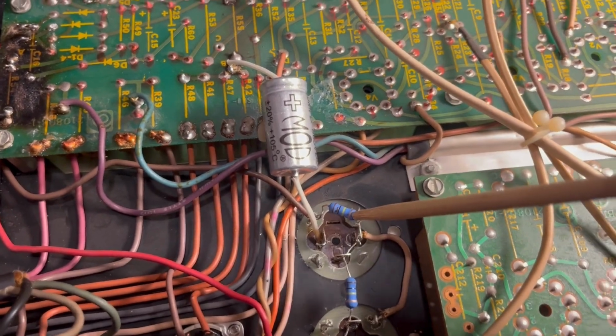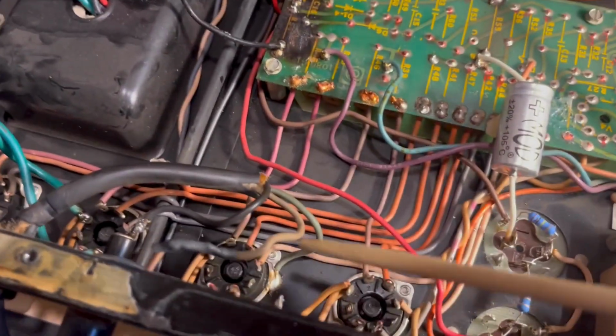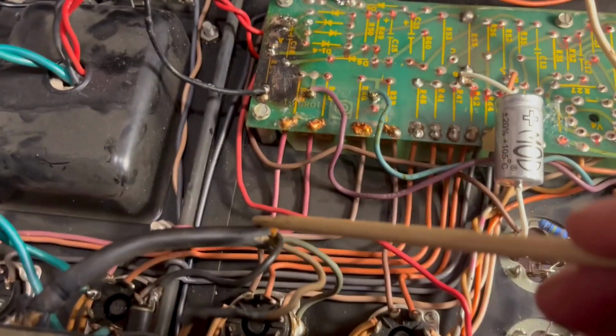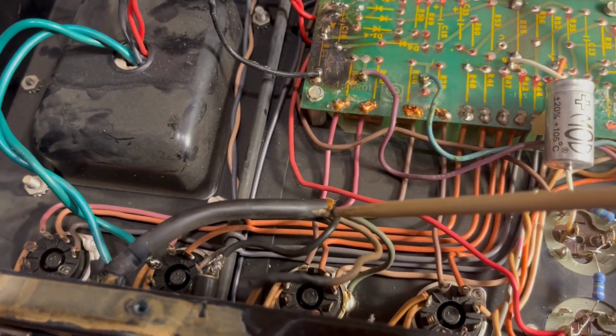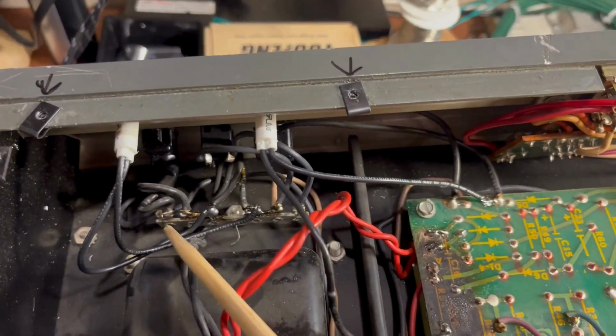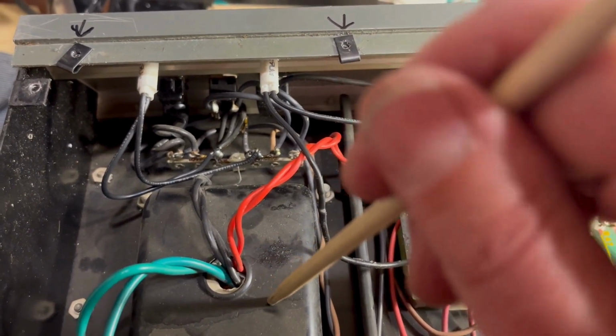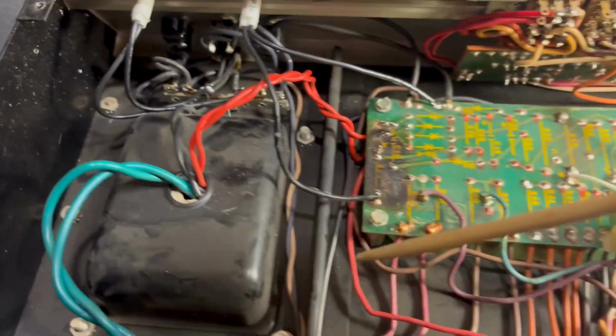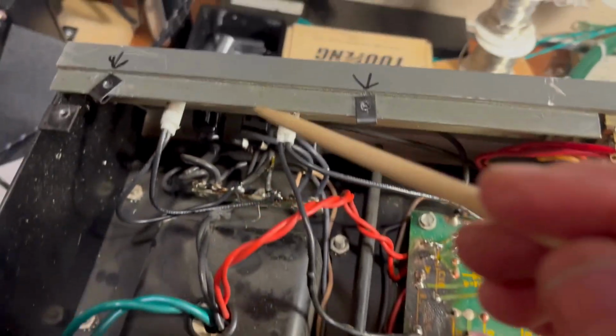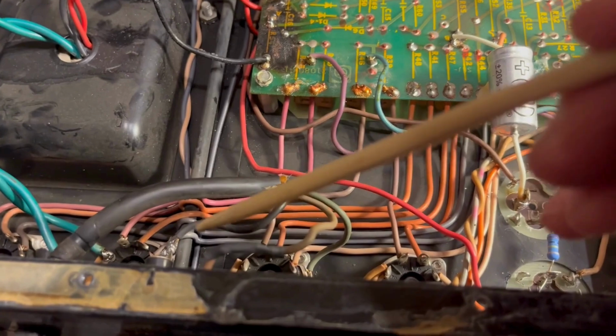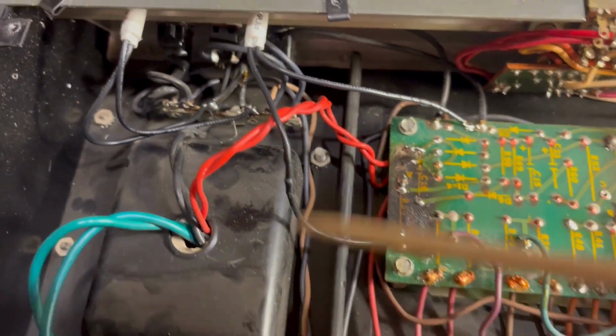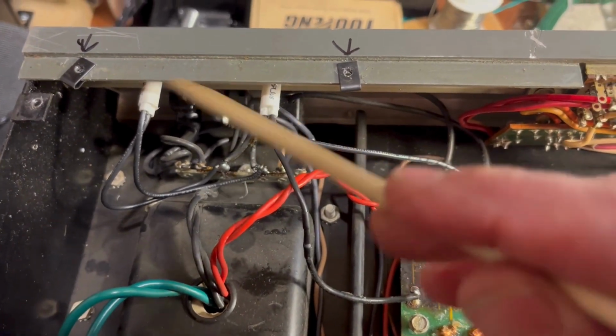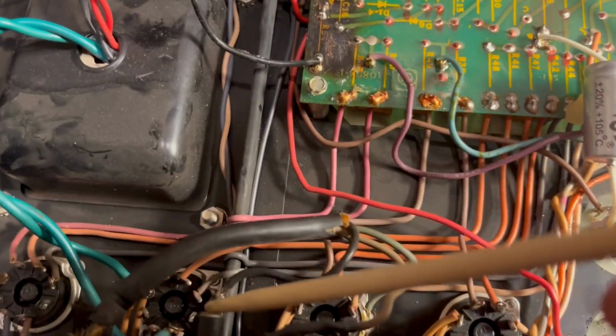So my next step in alleviating this hum is going to be rewiring and getting the primary circuit wired correctly. Right now the hot wire comes straight to the fuse, then up to the switch, then to this terminal strip to energize the transformer. But what we want to do is come in and go directly to the switch, then to the fuse, and then to the transformer. That's because when the switch is off, we don't want any power in the system. The way it's wired right now, the switch could be off, but there would still be power here.